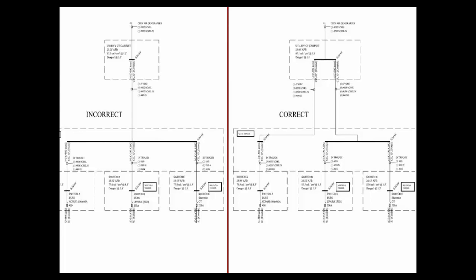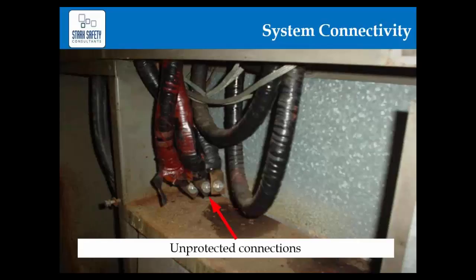The original data was mapped and marked as shown on the left, which is incorrect. On the right you can see that some of the connections, the feeds and loads, were actually split off here in reality. That could play a big part in available fault current and the actual arc flash calculations. So it's important that we map the system out correctly - not to mention it could play a role in connectivity and lockout tagout, since we may not have a good drawing for that either.